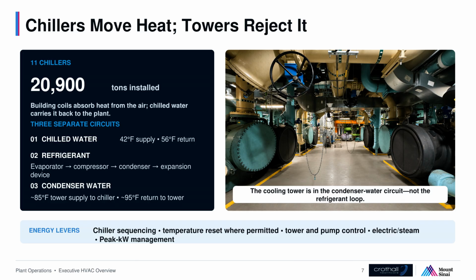Third is the condenser water loop. Water returns from the cooling tower to the chiller at roughly 85 degrees, absorbs the rejected heat in the condenser, and travels back to the tower at roughly 95 degrees. At the tower, airflow and evaporation reject that heat to the atmosphere. Those temperatures are typical reference values, not fixed set points. The key point is that the tower is part of the condenser water circuit, not the refrigerant loop.